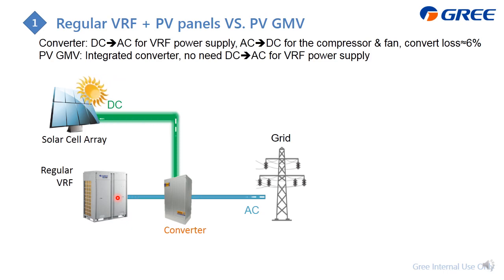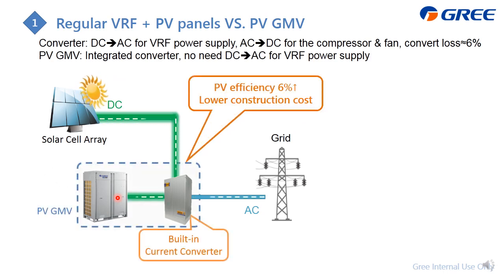But for our PV GMV, we also have a converter, but it is built in - this is actually the regular VRF, and we combine them together. So you just need to connect the power from the grid power supply, which is AC, and the power from the PV panels, which is DC. We can use the DC to drive the inside compressor and fans directly, so we can eliminate this 6% loss. This also improves the construction speed, as you don't need to set up the converter, so it's easier to install.